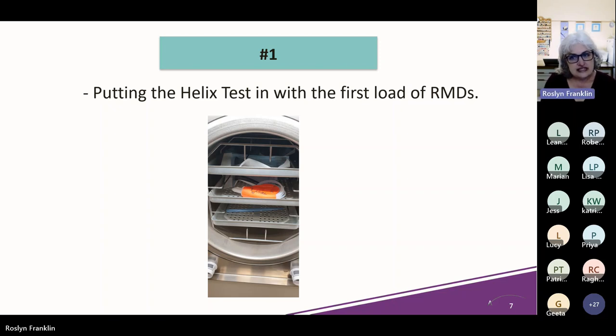This second test is an air removal and steam penetration test—quite a mouthful, isn't it? This test is either a Helix test or a Bowie-Dick test, and it's required to be run every day in that autoclave, regardless of the brand. It tests how well air is removed from inside the chamber and from inside any instruments, which is done at the start of the autoclave cycle.